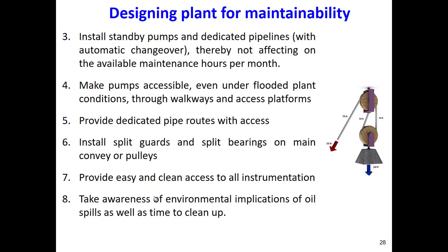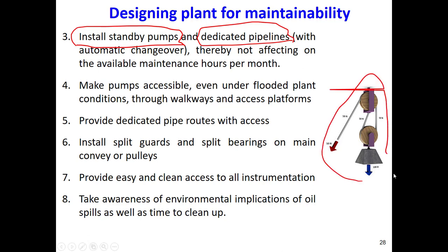Those are also some additional points about designing a process for maintainability, for maintenance. As I said, for the pumps and the compressors, we always have to install standby equipment. Most of the time for the pumps we install one parallel pump or one parallel compressor. So when the pump needs maintenance, we switch to the parallel pump. We do the maintenance, we fix it, and then we switch back to the main pump. We need to design such things in the process. And even for the pipeline, we have to dedicate some pipeline that is used for purging, for maintenance. Then, as I said, we should design lifting devices and moving devices to move the equipment, and locate them to be accessible.